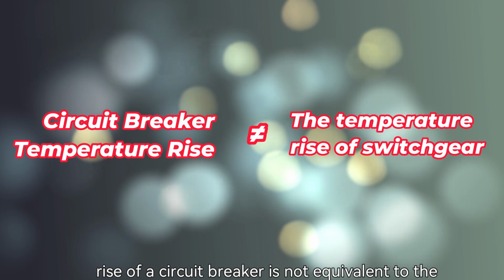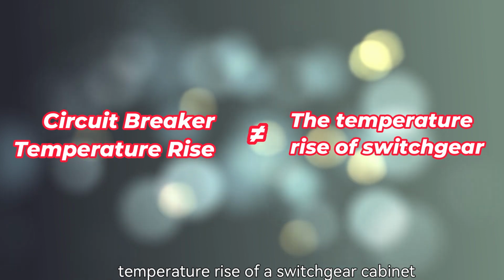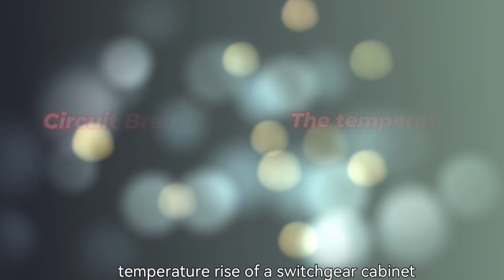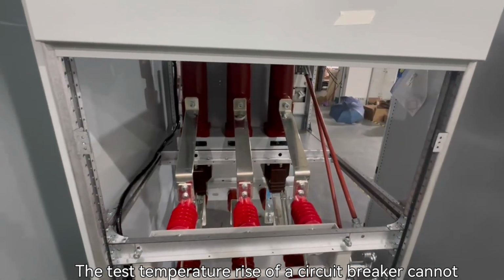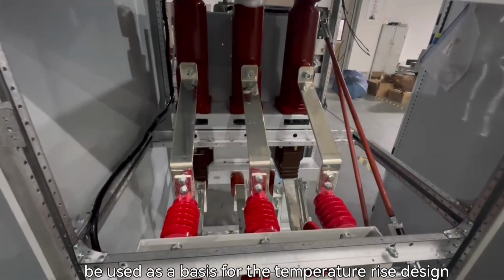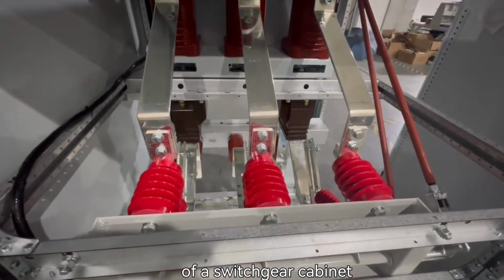Here is a brief explanation that the temperature rise of a circuit breaker is not equivalent to the temperature rise of a switchgear cabinet. The test temperature rise of a circuit breaker cannot be used as a basis for the temperature rise design of a switchgear cabinet.